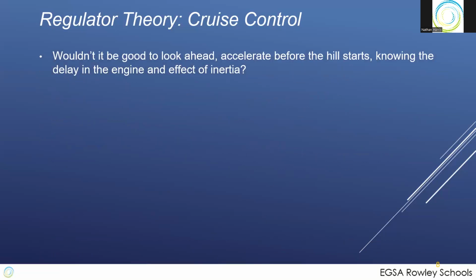So that's the proportional, like the 4 or the 50. That's the gain. The integral actually slows it down a little bit during transient conditions. But wouldn't it be good if we could look ahead and see what's coming? You do when you drive, right? You see a hill coming, you might step on the gas a little bit. It's something called feed forward.